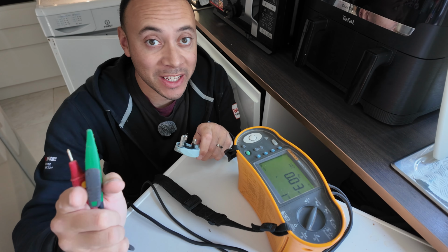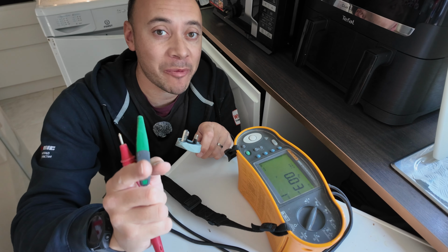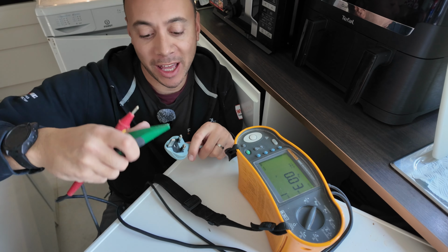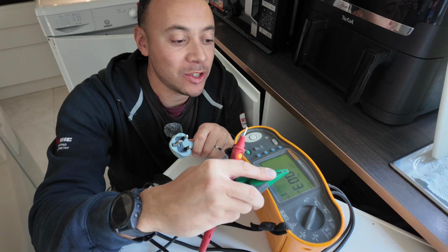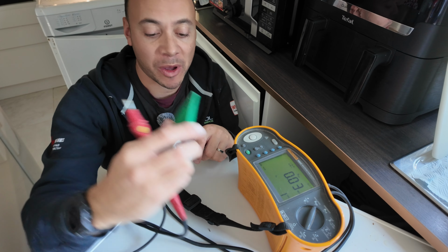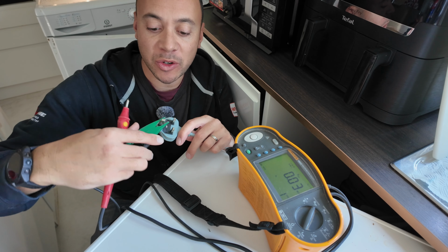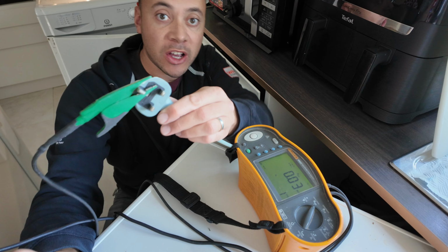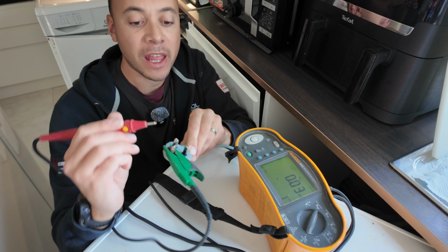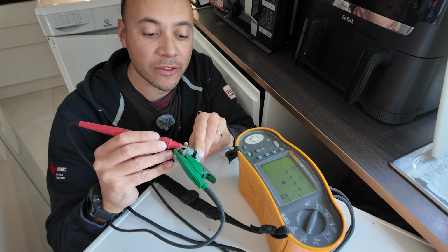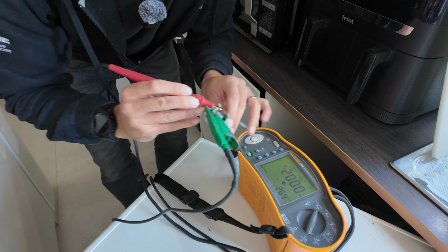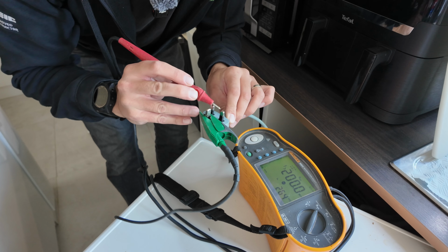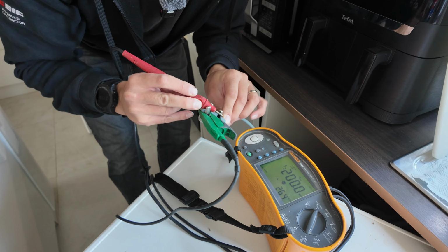Right, so I'm looking into the appliances right now. I don't have my PAT tester with me. But what I can do is use the insulation resistance tester from my multifunction tester and put 250 volts, doing the same again, between earth to neutral and earth to live. I can simply go straight off the pins, clamp onto the earth pin, and do earth to neutral, earth to live on the appliances individually, and see what I get. And this one, 200 megs and 200 megs there.